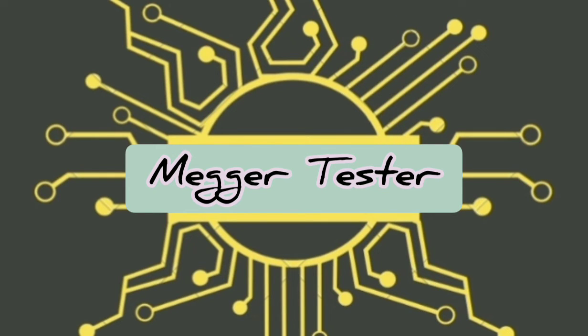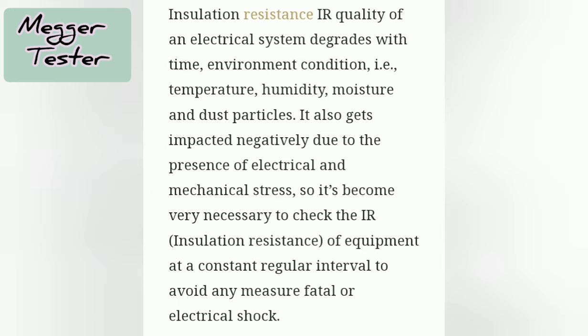The next measuring instrument is the Megger Tester. It measures insulation resistance. The IR quality of an electrical system degrades with time and environmental conditions, for example temperature, humidity, moisture, and dust particles. It also gets impacted negatively due to the presence of electrical and mechanical stress, so it becomes very necessary to check the IR of equipment at regular intervals to avoid any fatal accident or electric shock.